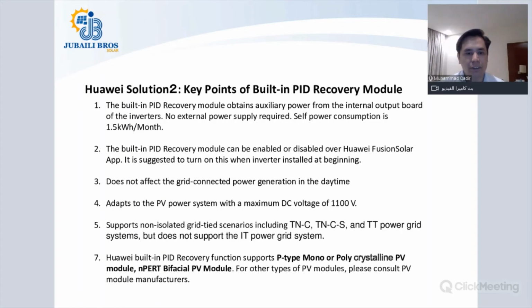So the key points of the built-in PID recovery module. The built-in PID recovery module obtains auxiliary power from the internal output board of the inverter. No external power supply required. Self-power consumption is 1.5 kWh per month per inverter. The built-in PID recovery module can be enabled or disabled in the Huawei FusionSolar app.